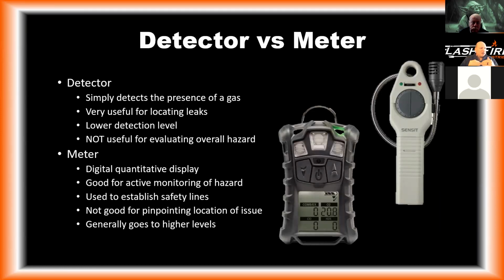When we talk about a meter, it's a quantitative display. So I can say, okay, I have 15% of the LEL or whatever the number is. It's good for active monitoring of the hazard. We use it to establish safety lines, but it's not going to pinpoint the location of the leak very well. The meter will go to much higher levels as well than the detector will. So it's important that if you have these, you use them in conjunction with each other, and you don't just take the leak detector in or just take the meter in, but use them together.